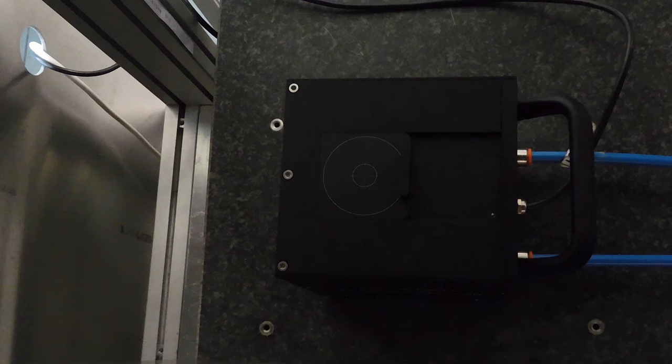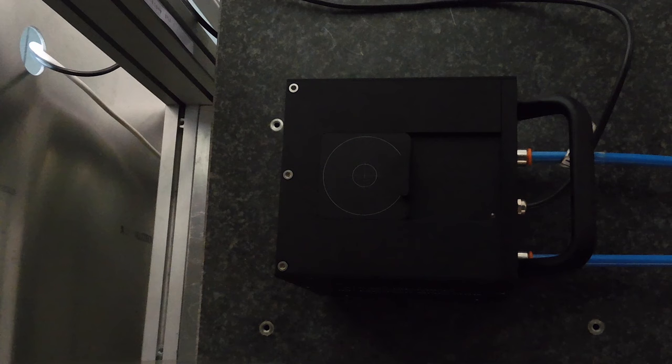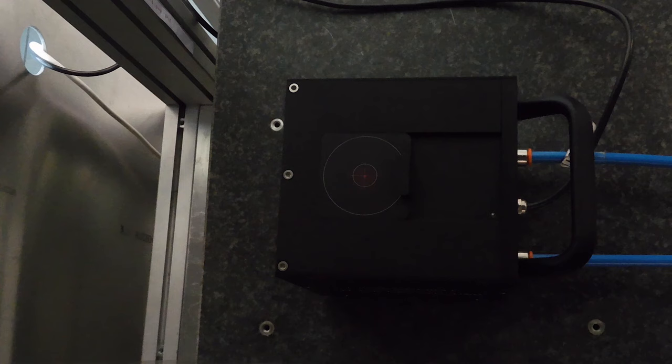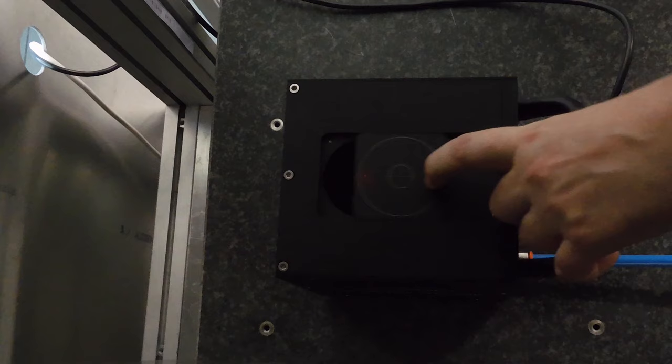In order to align the system, we use the aiming beam from the laser. We switch it on and we align it using the cross on the cover. When we have aligned it, we open the cover and we are now ready for the measurement.